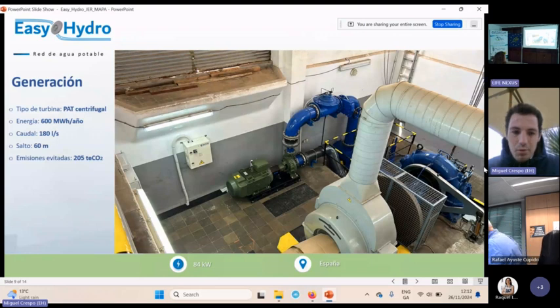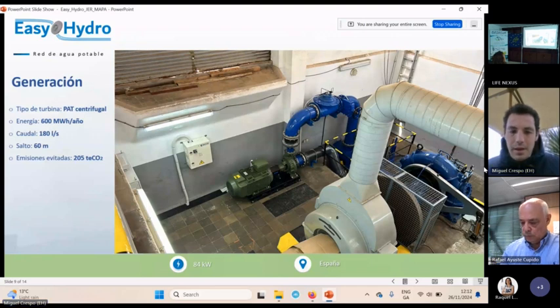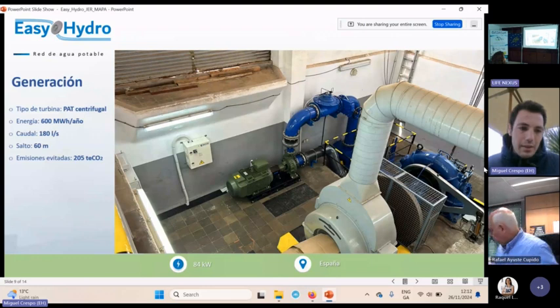And here is a 110 kilowatt PAT installed in parallel to the Francis turbine. It's been running already for 6 months, and it's generating something between 75 and 80 kilowatts of electric power, taking advantage of 180 liters per second and 60 meters of net head. So yearly, we are generating 600 megawatt hours per year. And basically, we have brought back to life this whole hydropower plant, and started generating some megawatt hours after 5 years of dry seasons.